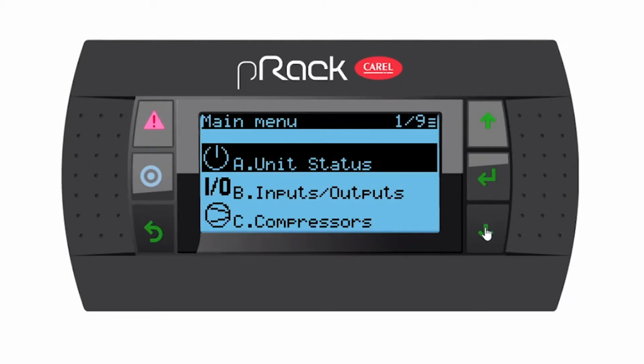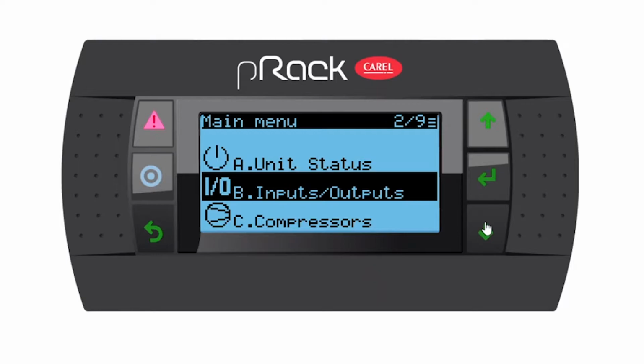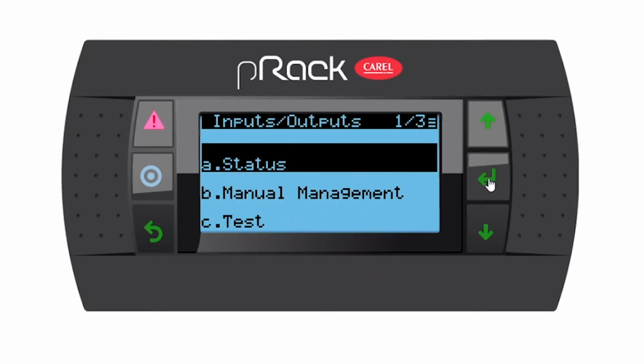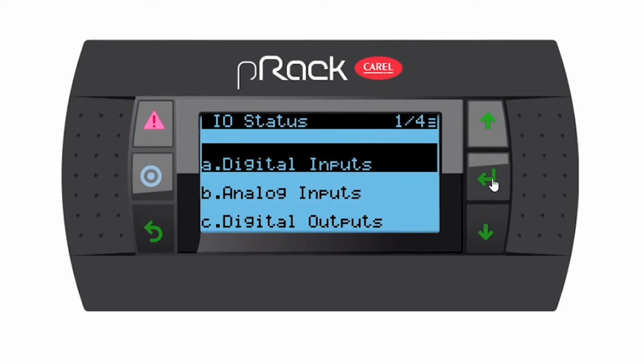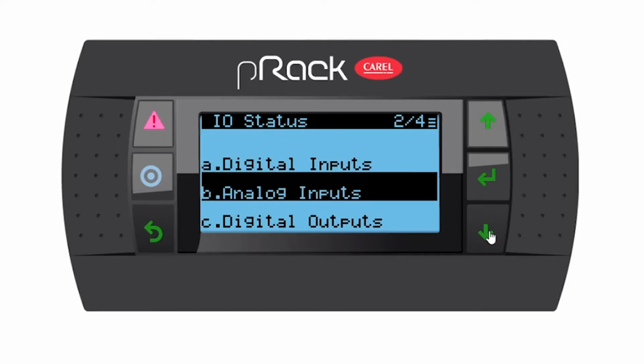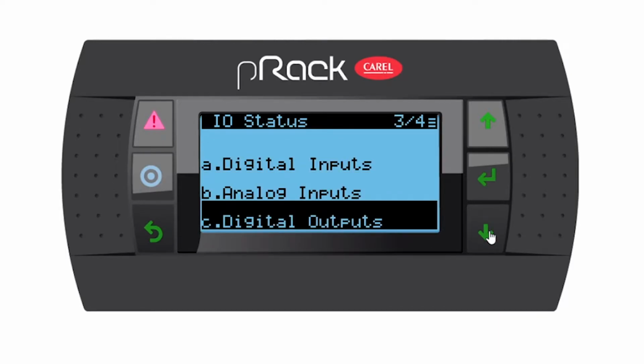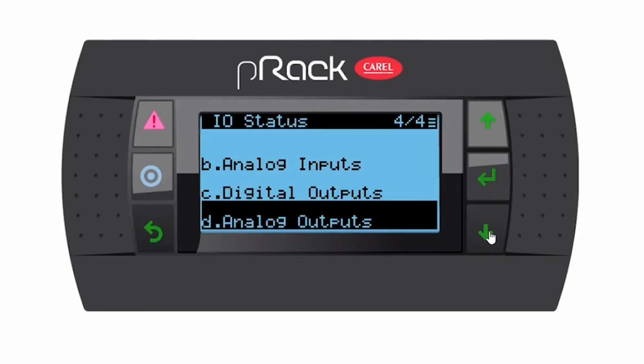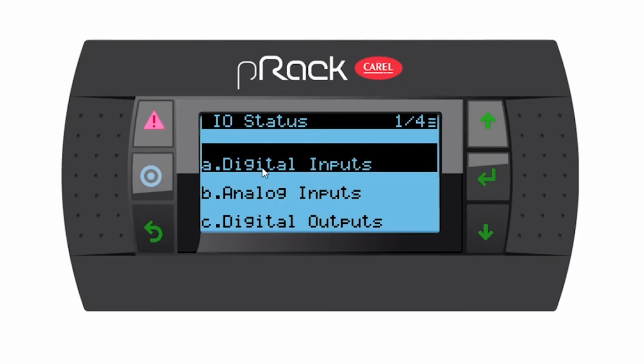In the main menus, let's go down to main menu B, inputs and outputs, and enter. This is a sub menu. We've got status, manual management or test. But because we're still setting up the controller, I would like you to go into status. So A, enter. Then we have the four sub-menus: digital inputs, analog inputs, digital outputs, and analog outputs. I always like to start at the top, so let's start with the digital inputs.